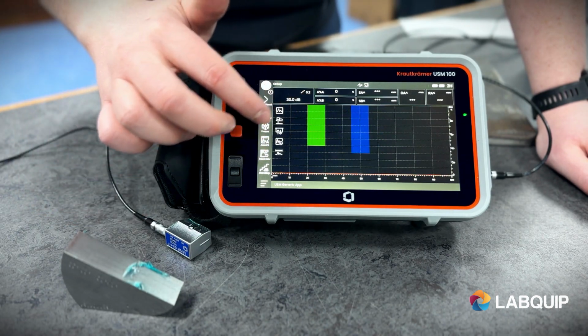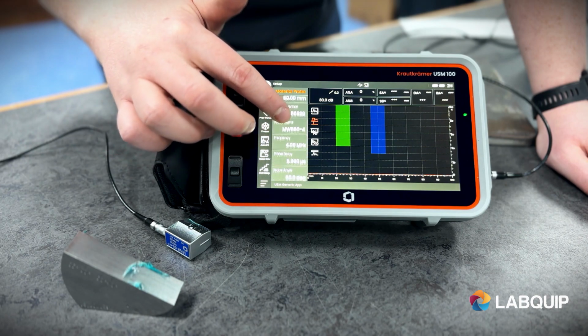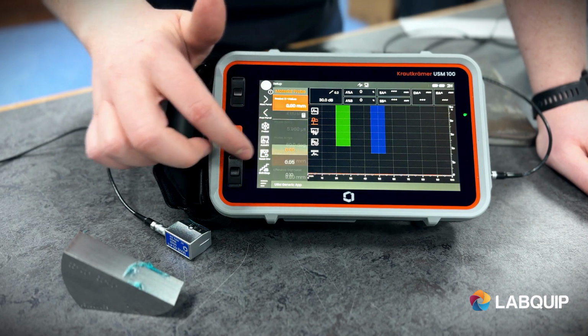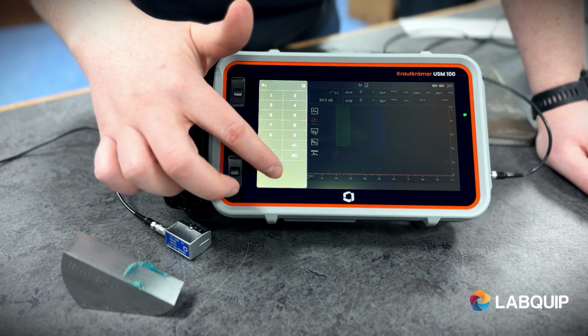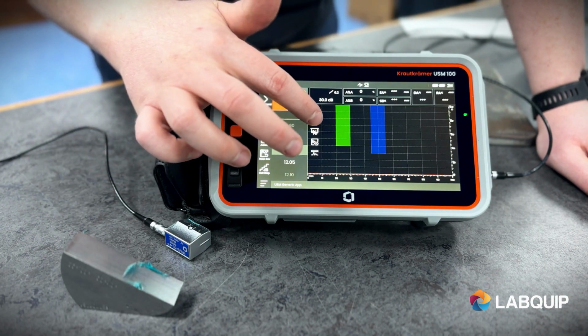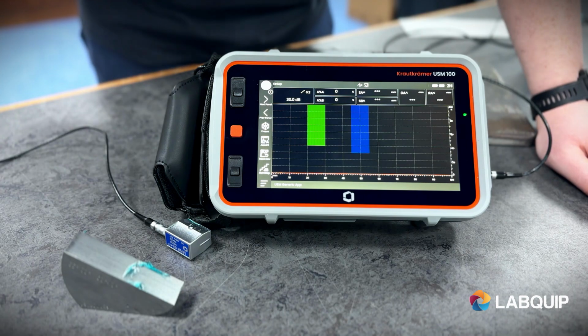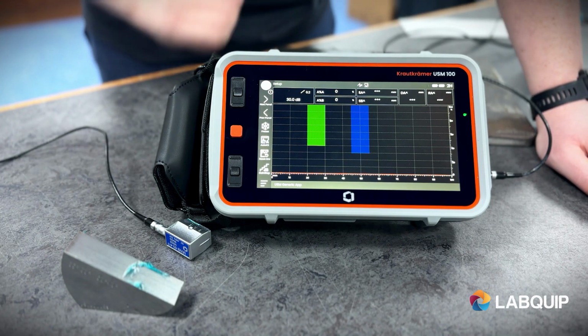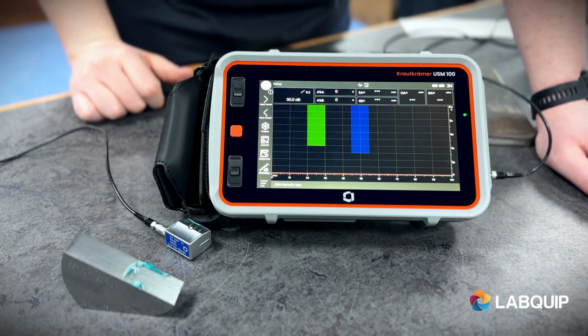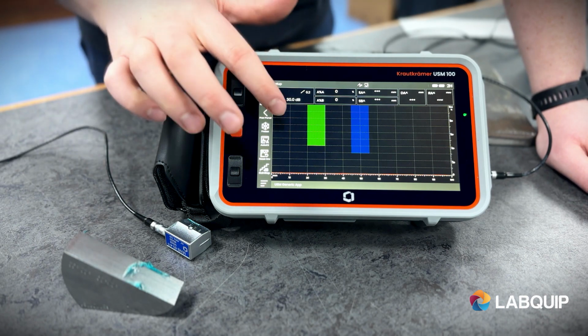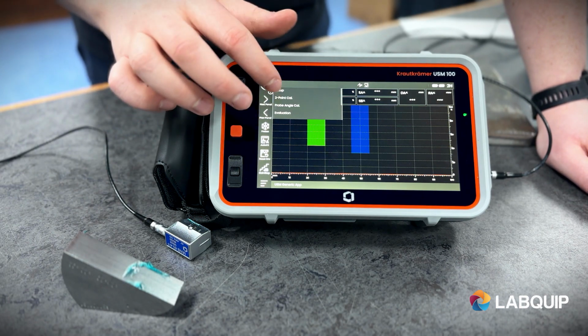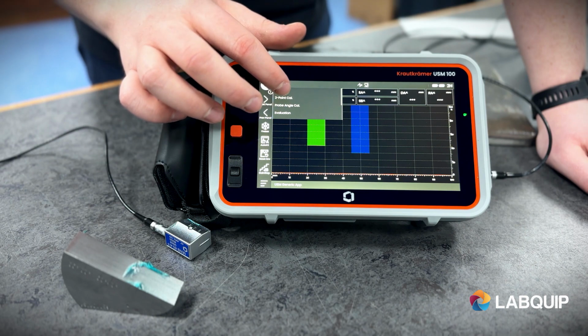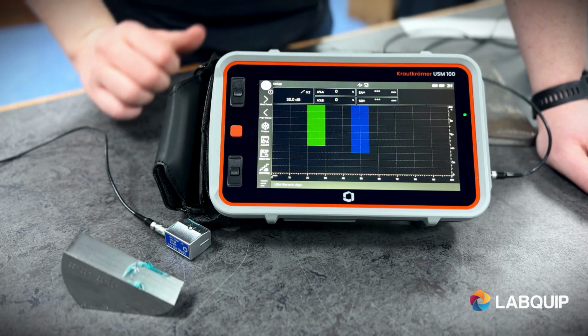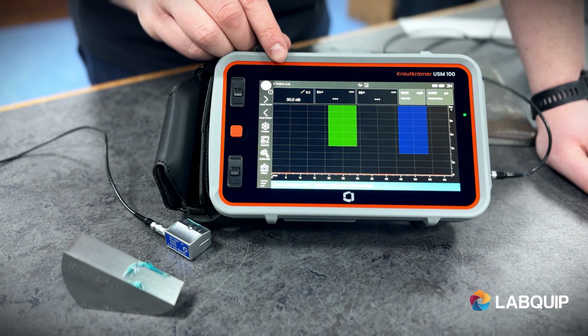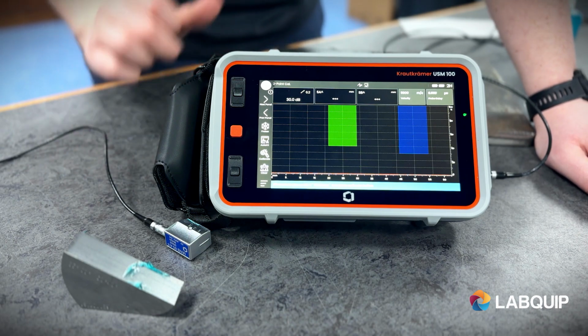Actually, sorry. We also need to tell it what the X value is of the probe. So I know the X value of this probe is 12 millimeter. So I'm just going to put this in and then hit OK. Now the X value won't matter for this at the moment, but when we get further into DAC curve training and other higher level feature training, it will become important. So once you have the setup done, you simply can go on to your 2-point cal this way, or you can hit next panel up at the top. Next panel brings you over to your 2-point calibration.